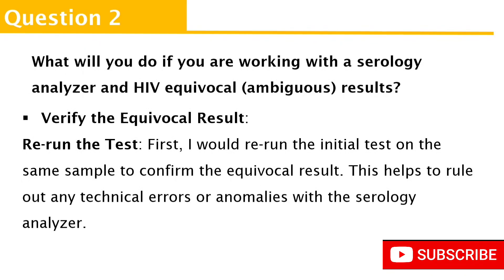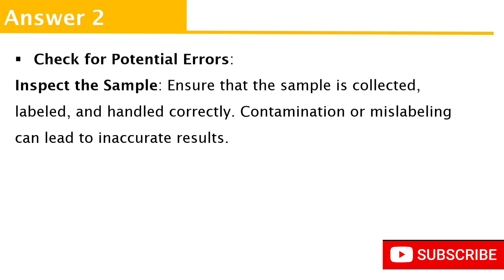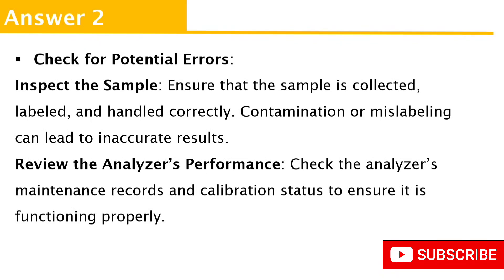It is also important to check the possibility of potential errors and rule them out. Look at the sample — is there anything wrong with it, such as mislabeling or contamination? If nothing is wrong with the sample, you might need to review other processes. Check the analyzer: is it working the way it's supposed to? This is where you look at maintenance records and calibration methods. If there are non-conformities, carry out maintenance and calibration, then repeat the test.